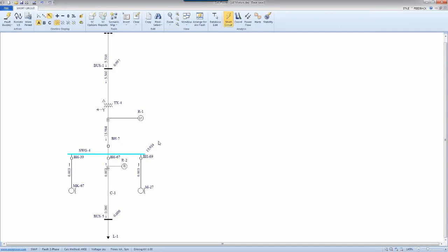Let's just go a little bit more and look at the exams. But eventually, there would be a time that this current goes entirely to zero. Then you can go back and integrate that current over the time, or you can calculate the incident energy for each step and then add them up, and that would become your entire incident energy.